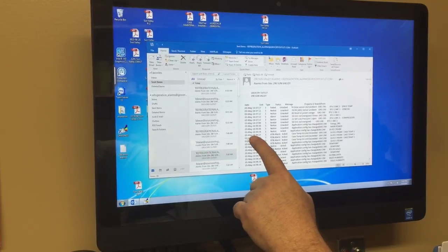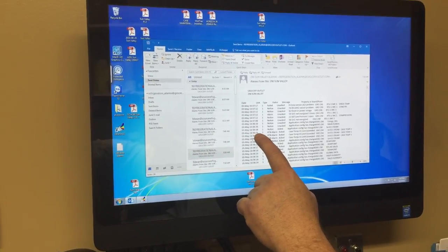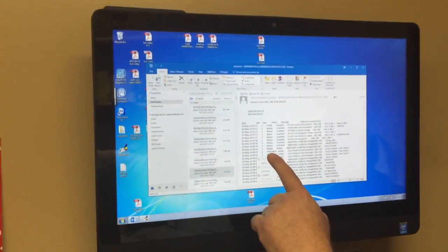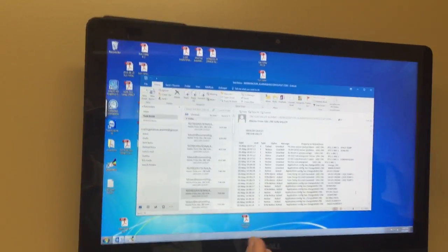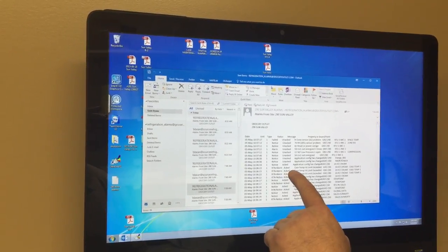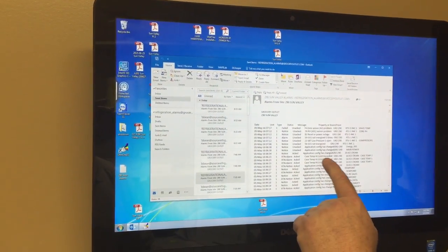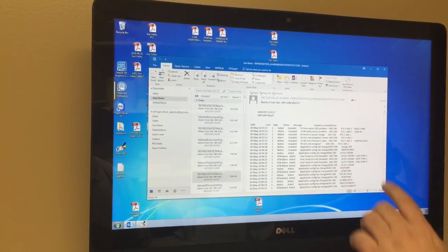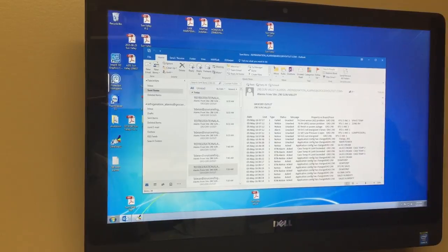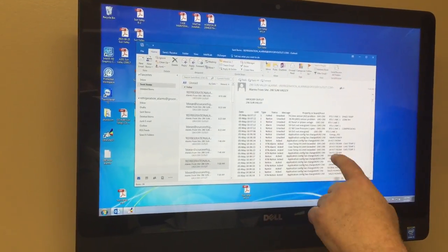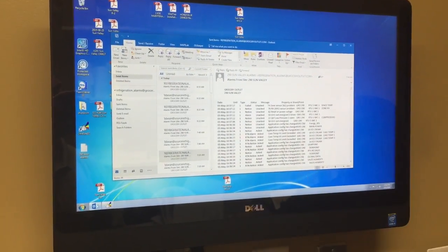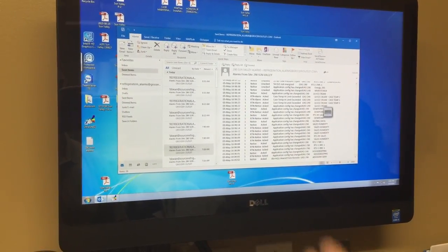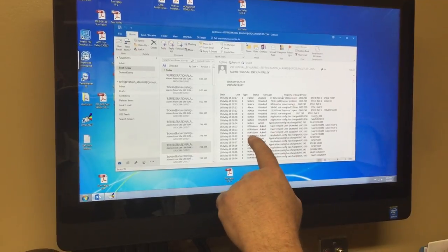As an example, on May 5th, 2016 at 6:23 in the morning, we had a return to normal. RTN means return to normal, which means everything's back to normal. Alarm, it's been acknowledged, and it was a high case temperature on system 1A ice cream. And it was case number 2 and then 1 and 3. So what it's telling you is that this was in alarm mode, it's now been cleared and returned to normal, and there's no more active alarms on it. RTN means return to normal.